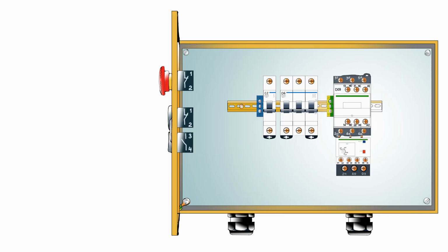We're going to start with the control circuit. The first connection is going to the top of the control circuit breaker, and this is coming from one of the phases on our main supply. So we draw from one of the phases to the top of our control circuit breaker, and then we get a connection from the bottom of our control circuit breaker to 95 on our overload relay.